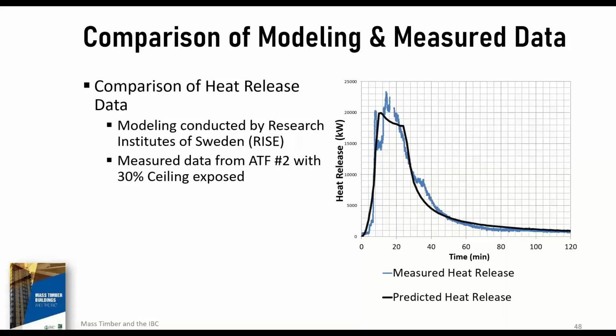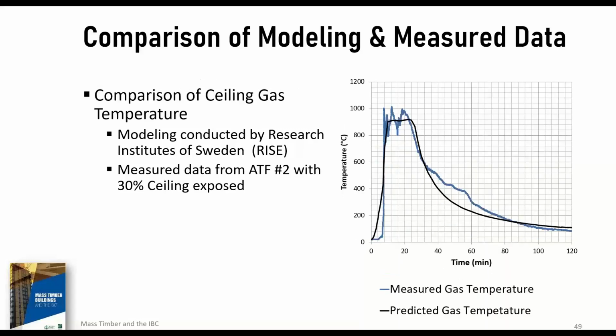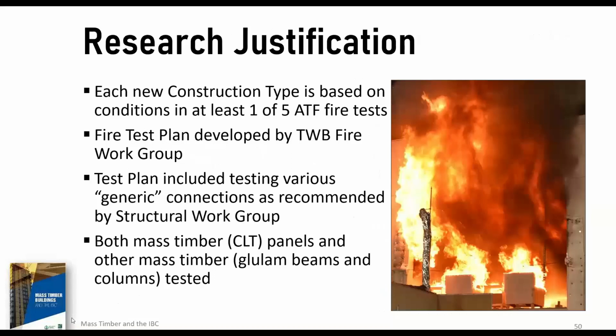I had seen, I think, 6 or 8 megawatt fires in testing before. I thought those were fantastic fires, just, you know, severe fires. Literally, this testing just blew me away how severe it was. The engineers tell me that 23 megawatts is the energy equivalent of 360 gallons of gasoline. So you can imagine the amount of damage and the energy released by consuming 360 gallons of gasoline. So a 23 megawatt fire is just a rip-roaring fire, a very severe fire, and the ATF, of course, took it very seriously with their additional safeguards we talked about previously.